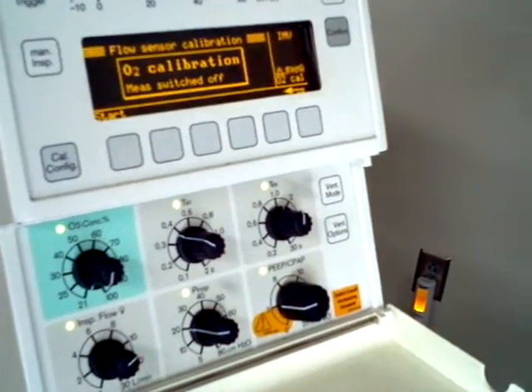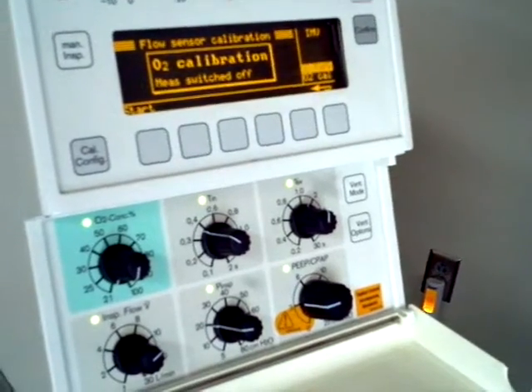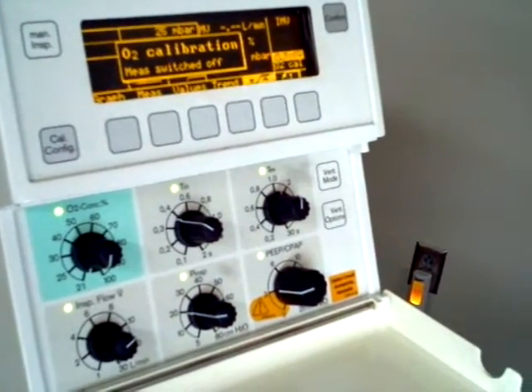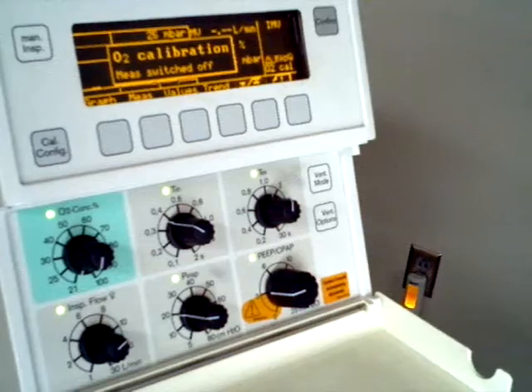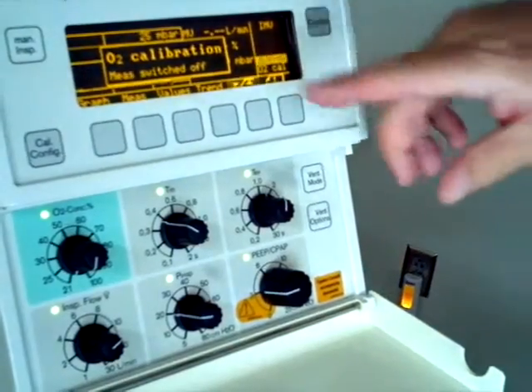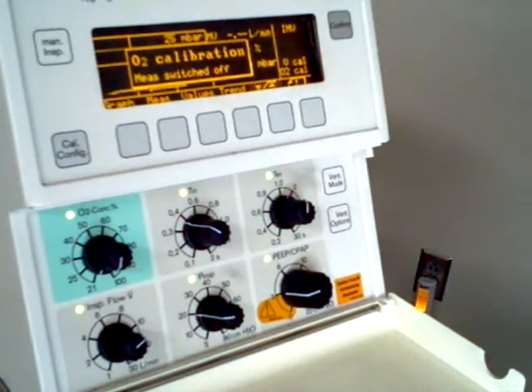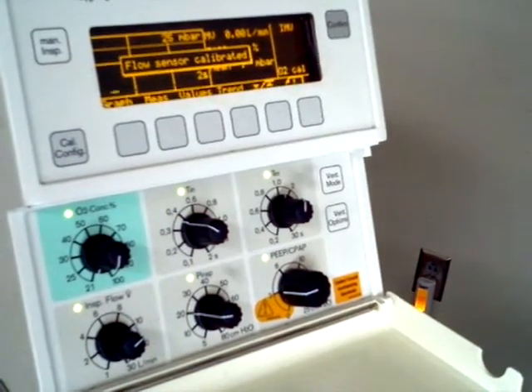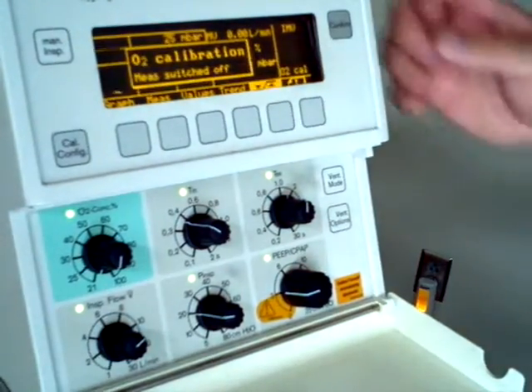I typically, sometimes it tells you to, but I think it's a good idea to take your flow sensor out, because what you're doing is zeroing it. So you don't want a lot of flow going through this while you calibrate it. And let's start over again here. And it takes just a few seconds. Flow sensor calibrated.